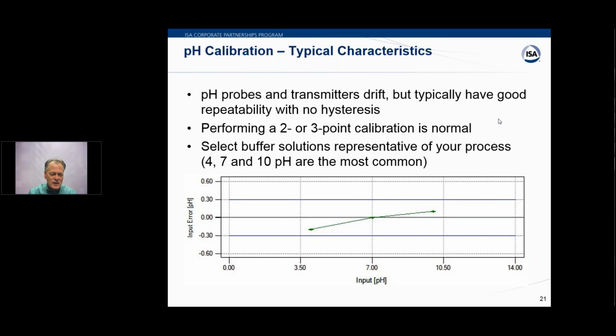We see with our customers, most people are doing a 2 or 3 point calibration, sort of a low, medium, high approach. So on this graph, we're showing 4, 7, and 10, which really are, I guess, the most common testing that we see out there. But you need to pick test points that fit your application, your process, and certainly you can get by with a 2 point check that's around your normal operating process pH.